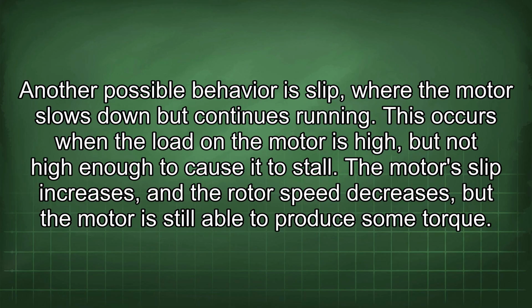Another possible behavior is slip, where the motor slows down but continues running. This occurs when the load on the motor is high, but not high enough to cause it to stall. The motor's slip increases, and the rotor speed decreases, but the motor is still able to produce some torque.